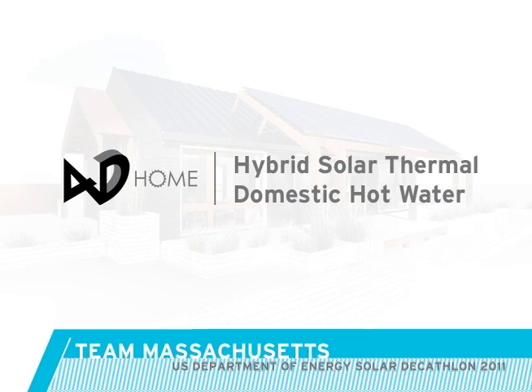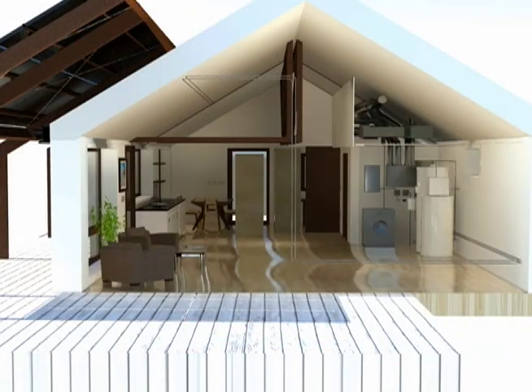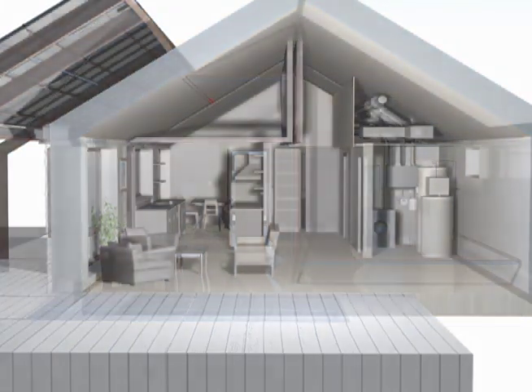Our 4D home uses innovative solar thermal collectors to help heat our domestic hot water. Unlike conventional solar thermal systems, which have a separate array mounted on a roof, our collectors are mounted directly behind the back surface of our PV modules. As the temperature of the PV module increases from exposure to sunlight, this otherwise wasted heat is transferred from the PV panel to the fluid flowing through the hybrid collector.